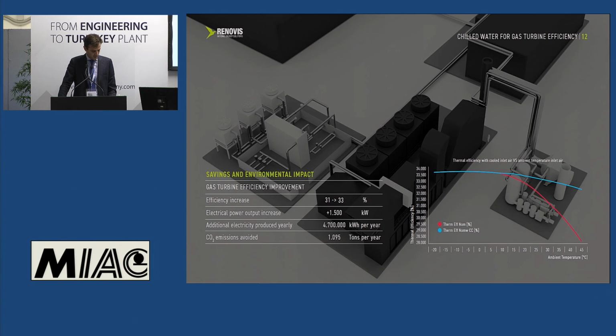The absorption chiller, which is based on lithium bromide technology, generates a cooling capacity, as I said, of 1.9 megawatts of cooling power. This means that it is able to bring the efficiency of the gas turbine back to nominal condition, as I said before, even in summer, and therefore without the ambient air temperature harming performance. So the performance remains the same during summer as in winter.